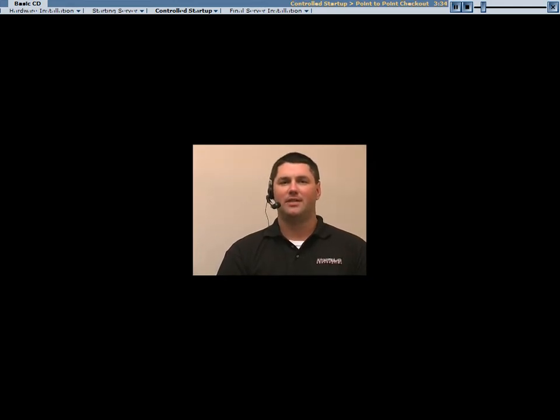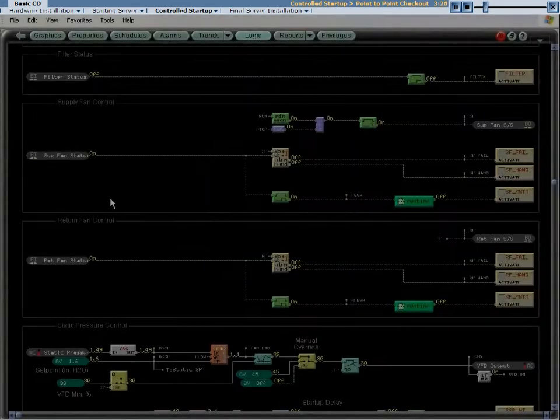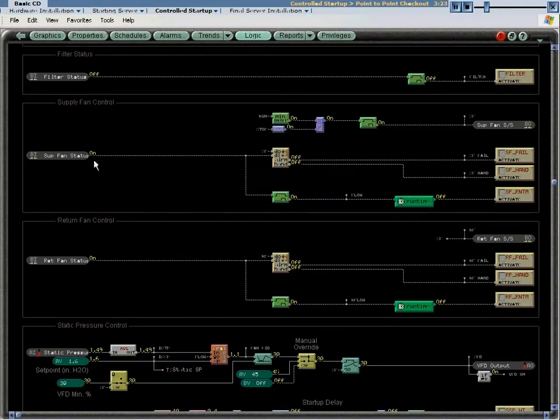For each BI, let's short the wires at each end device, such as a fan proof or a pump proof. Verify the binary input point is closed on the logic page. Open the binary input at the end device. Verify the binary input point is open on the logic page. Note: if the readings on the logic page are reversed from actual conditions, the polarity, normally closed, normally open contact position, is set incorrectly. Change the polarity and check the point again.